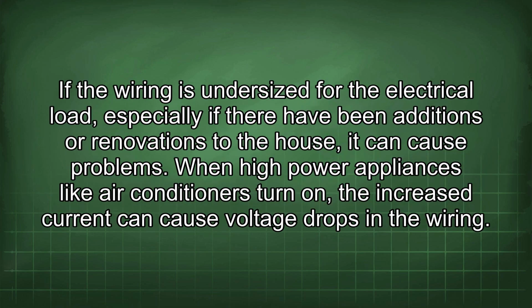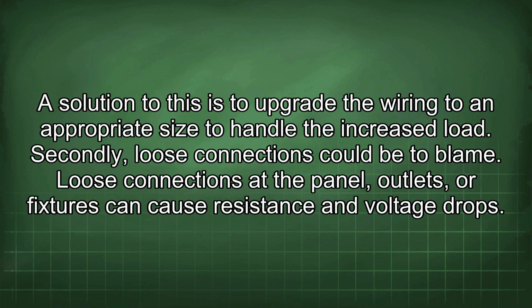If the wiring is undersized for the electrical load, especially if there have been additions or renovations to the house, it can cause problems. When high-power appliances like air conditioners turn on, the increased current can cause voltage drops in the wiring. The solution to this is to upgrade the wiring to an appropriate size to handle the increased load.